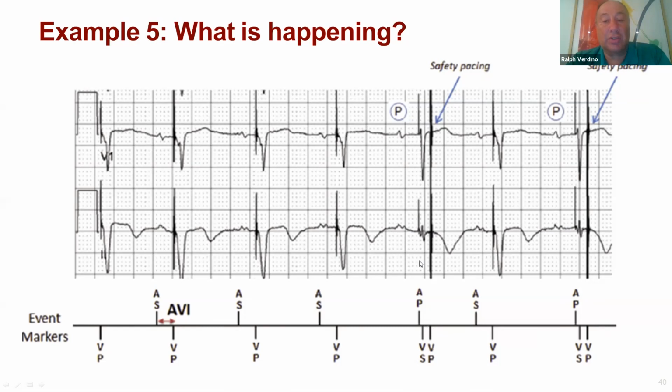So then the ventricular channel saw that ventricular sense, but said, wait a minute, I just paced in the atrium. How could I get a V that quickly? It didn't conduct down that quickly. But, you know, I don't think it really is. I could put a ventricular pace down, but if I do, and it really was for some reason a QRS, then I'd be pacing on the T wave. And years ago, we really didn't like to pace on T waves when we had very high output devices. So it said, I'm not going to do that. I'm going to give a very short AV interval pace.